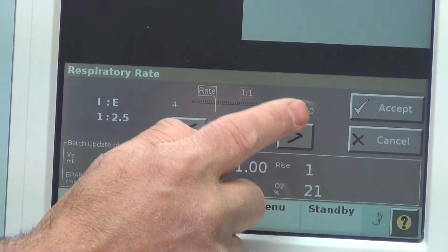Respiratory rate, again ordered from the physician. We've been using 18, we'll do that, accept. I time, we're just going to leave at 1 second. Rise time, we're just going to leave at 1 second. I time is the amount of time you spend in the inspiration phase of your breathing, and rise time is how quickly you get your flow from the machine. Next row underneath that, and notice that the ones we've changed are yellow and the other ones are white. When we activate it, they will all change color.